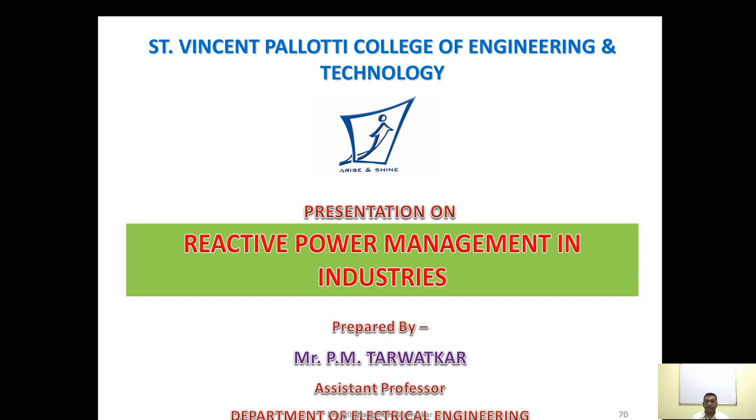Now in this particular video we will be focusing upon reactive power management in industries, because the power factor is a big issue and needs to be maintained at a proper value in all industries. Otherwise, if the power factor of the industry is very poor, then they have to pay penalties. The losses are increased. How this happens, what is the concept of power factor, and what are the various methods to improve the power factor or reactive power, we will be discussing in this video.